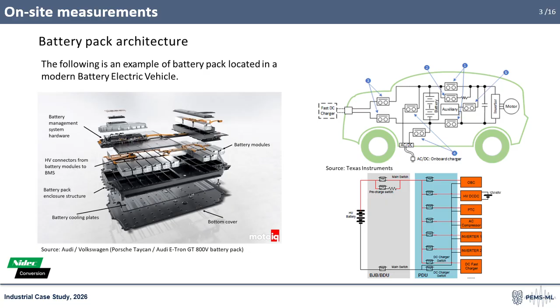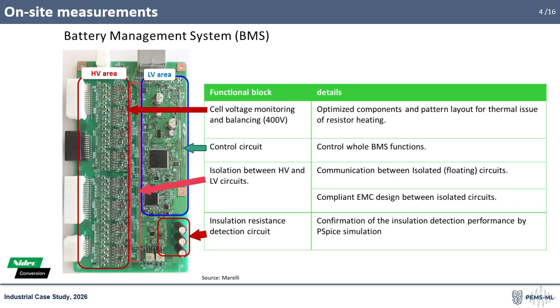The battery management system is the electronic control board with the responsibility of monitoring the status of all the cells inside a battery pack. The PCBA is divided into two parts: the logical part on the right, which operates at an extra low voltage of 12 volts, and the sensing part on the left, which measures the voltage of the cells. The two parts are galvanically isolated and communicate by means of isolation transformers.